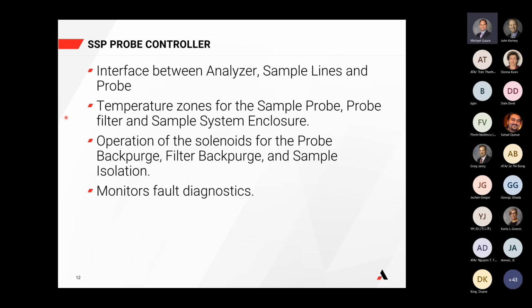Hopefully everybody on the call agrees that Rod has demonstrated that we have a probe that's capable of generating and maintaining a representative sample through both temperature and flow maintenance. And by flow maintenance, what I'm referring to is keeping the path clear of any particulates that may be getting into the system. And that's accomplished by doing the blowbacks at the filter as well as in the probe. But the logical question, though, and Rod alluded to it when he was walking through the probe's functions, is how is that managed? And the way we manage that is by utilizing what we refer to as our severe service probe controller, SSP probe controller here.